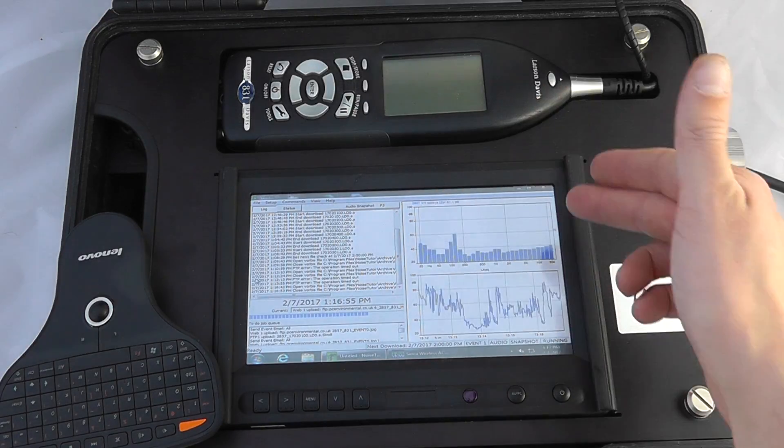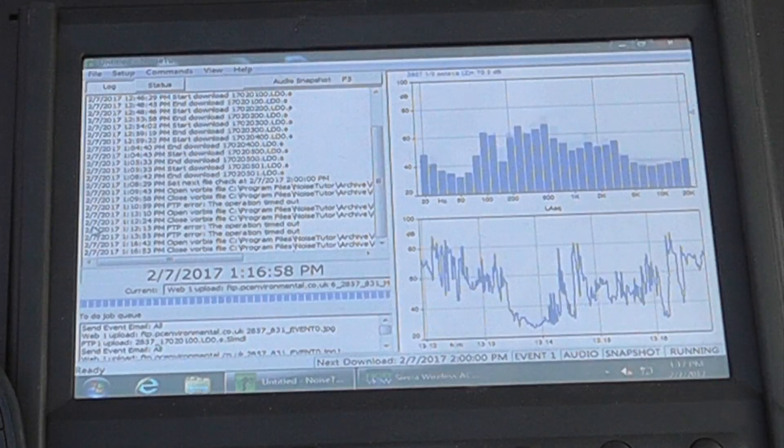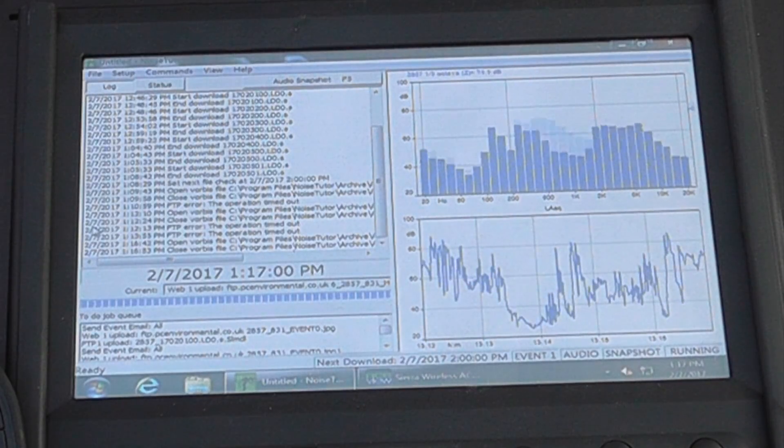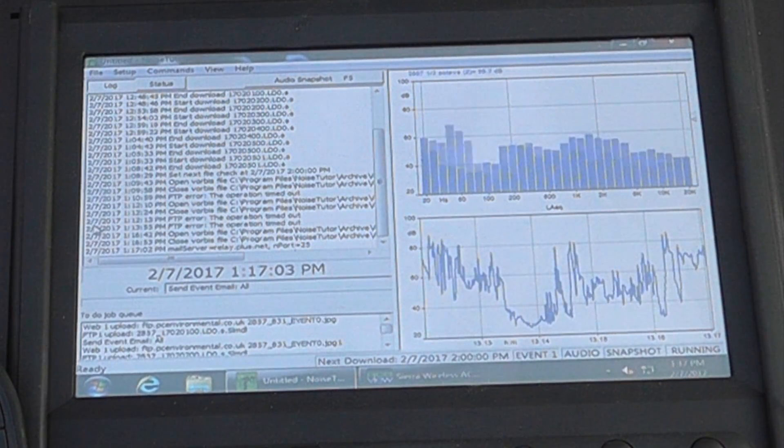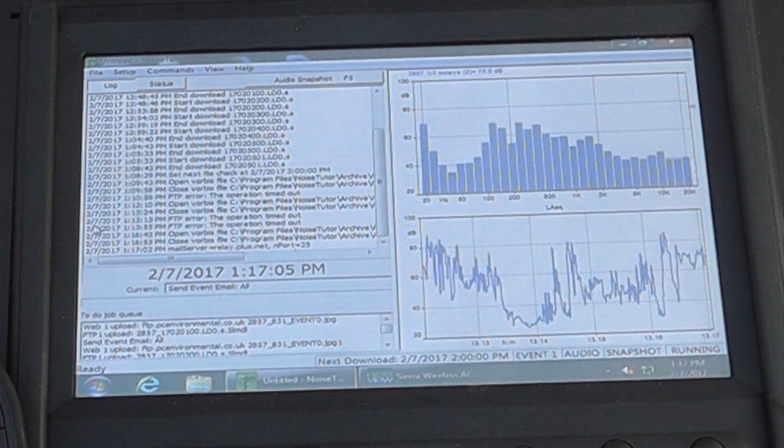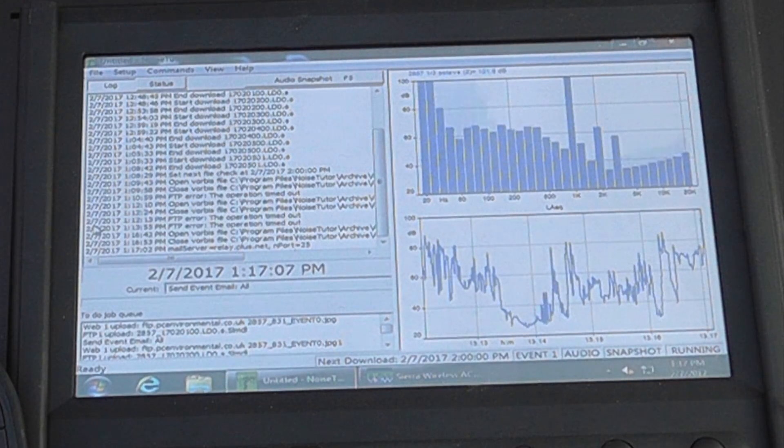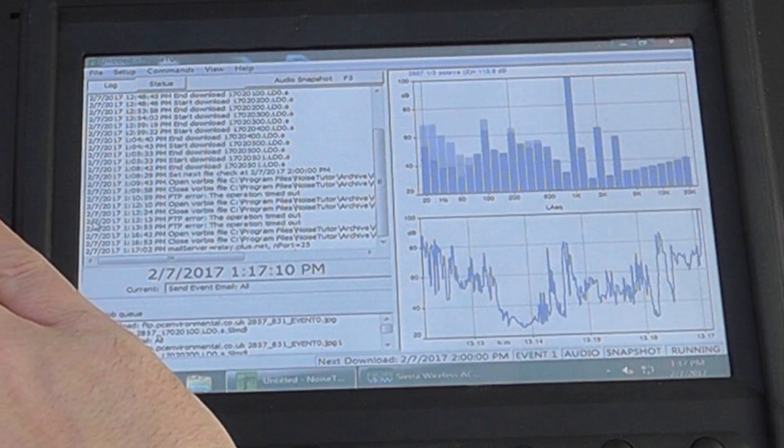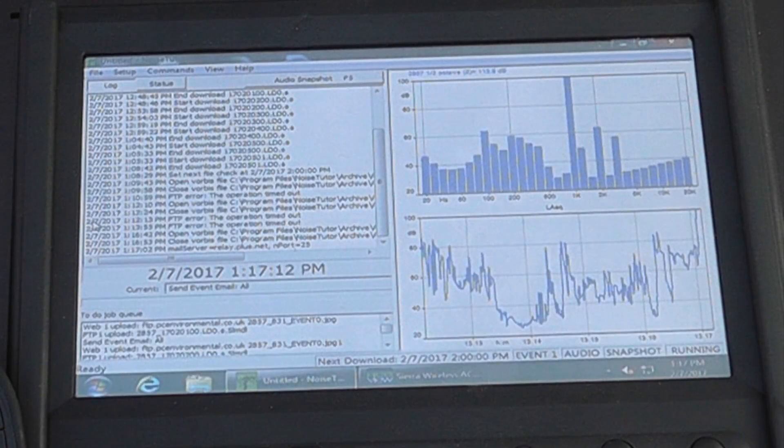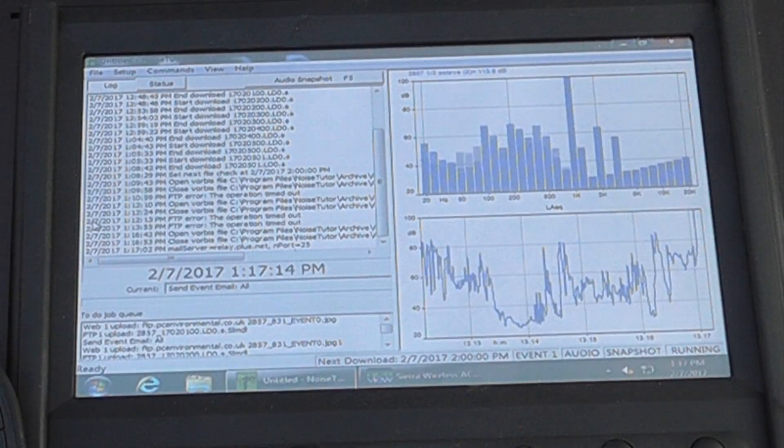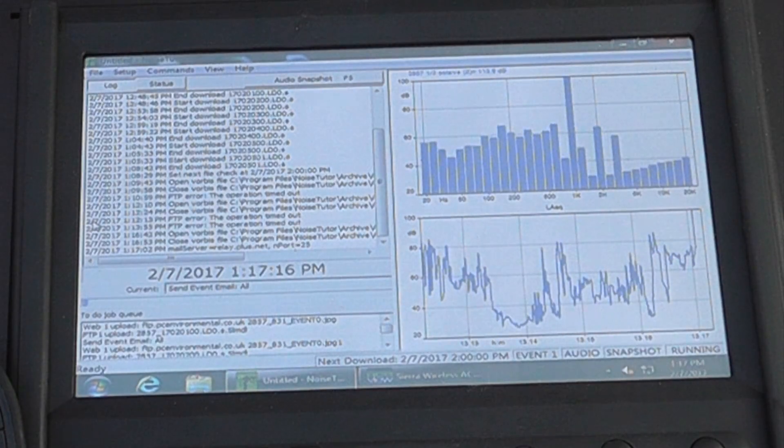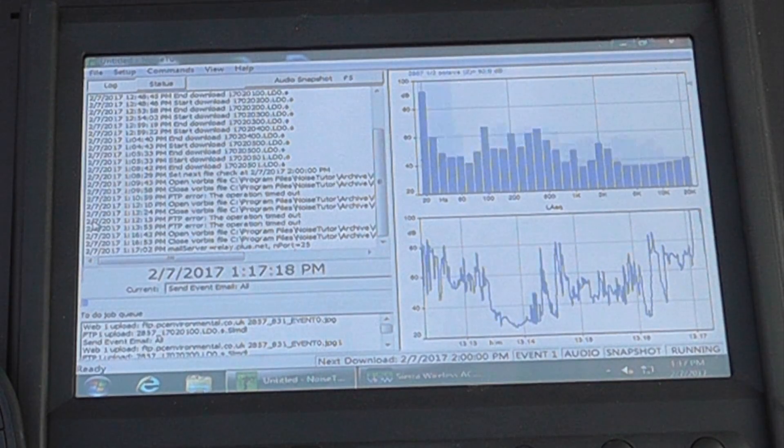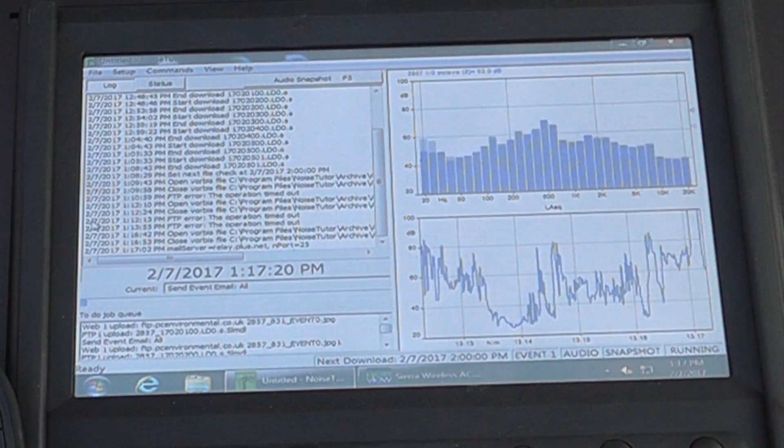We can see live monitoring of some third octave bands at the moment. I will introduce a 114 decibel reference tone onto the device and you'll be able to see we're getting a nice measurement at one kilohertz. This gives me a live reading of what's going on right now. I'll remove the reference tone and we can see we're getting a good octave band spectrum.